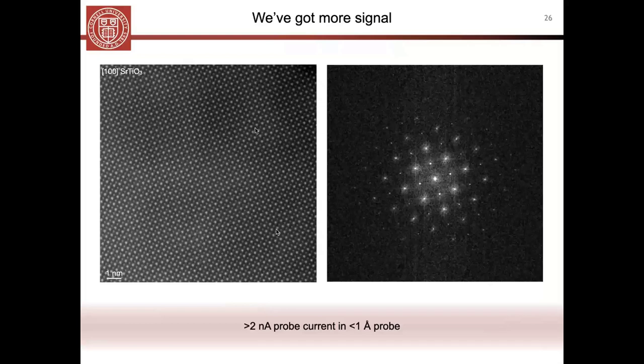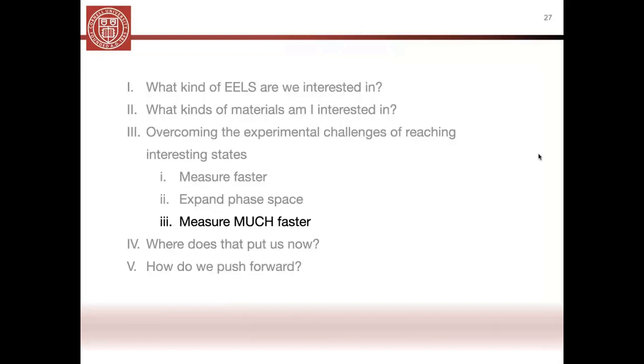But looking at the information transfer from this image, we see information transfer out to 64 picometers. So we're really packing a punch with this STEM probe, and that's how we put more signal into our sample in the same amount of time. That allows us not just to improve the signal, but to signal-limit ourselves and measure much, much faster.